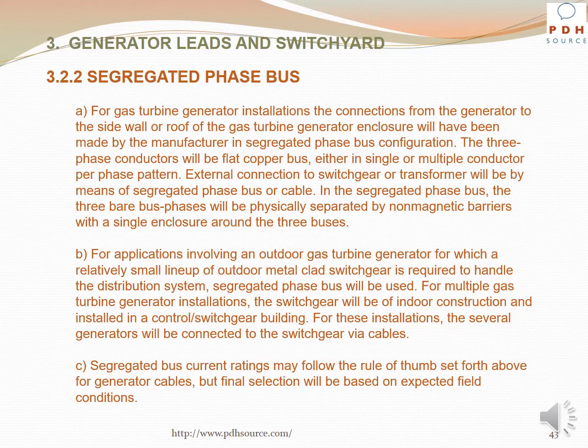For applications involving an outdoor gas turbine generator for which a relatively small lineup of outdoor metal-clad switchgear is required to handle the distribution system, segregated phase bus will be used. For multiple gas turbine generator installations, the switchgear will be of indoor construction and installed in a control switchgear building. For these installations, the several generators will be connected to the switchgear via cables. Segregated bus current ratings may follow the rule of thumb set forth above for generator cables, but final selection will be based on expected field conditions.